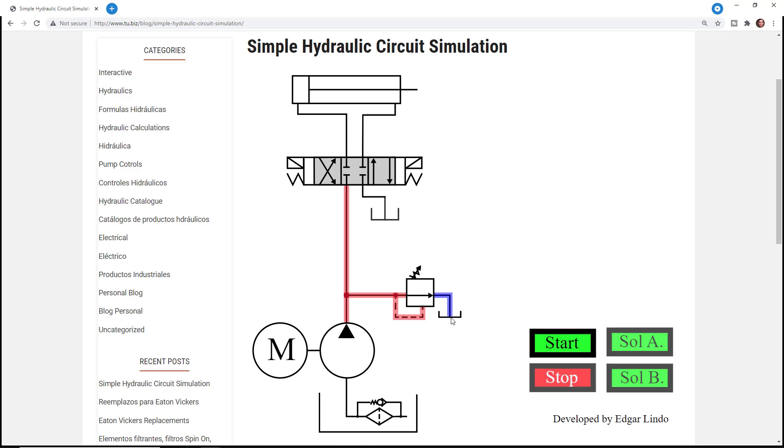I cannot put out any more fluid through here, so it has to go. The pump keeps pumping, but the fluid has to go somewhere and it goes through the relief valve maximum setting. It has to discharge under pressure to the relief valve.